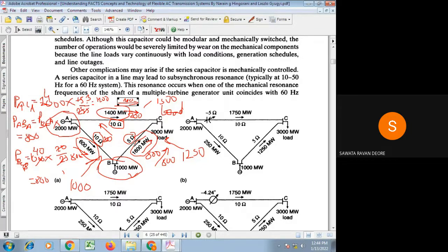Either you need to operate the system uneconomically or you have to go with some further action so that in future you will operate it economically. So the solution is, you have to upgrade this transmission line, अपग्रेड मतलब उसको हायर रेटिंग के लिए अपग्रेड करो, नहीं तो फिर उसके साथ पैरेलल में दूसरा लाइन डालो. अभी पैरेलल में दूसरा लाइन डालेंगे तो there is an issue of right of way and all that. The cost involved in that is very high. Again, the time required to complete that work is also in terms of years. So till that time, again, we have to operate that system uneconomically.